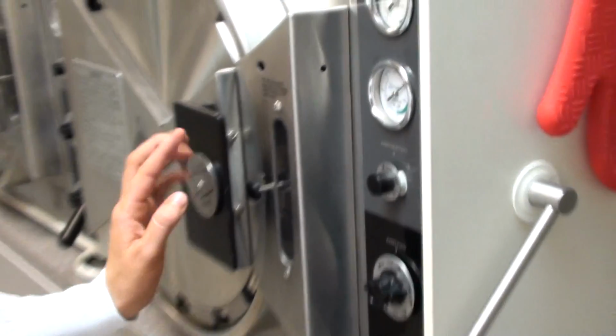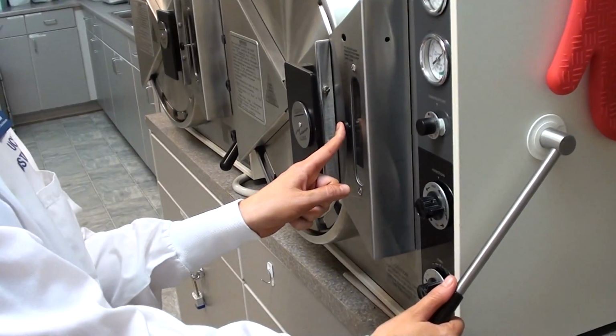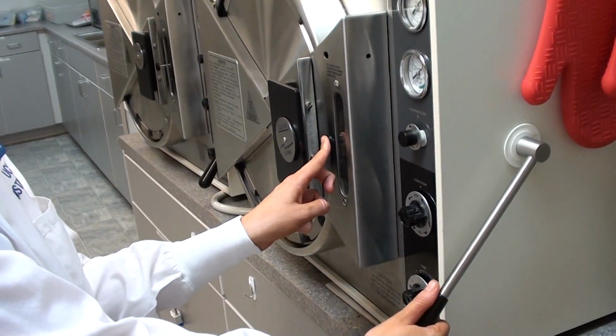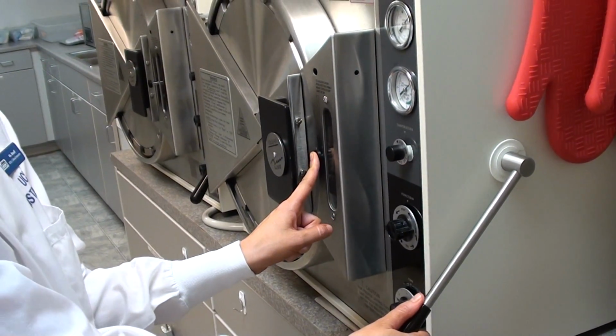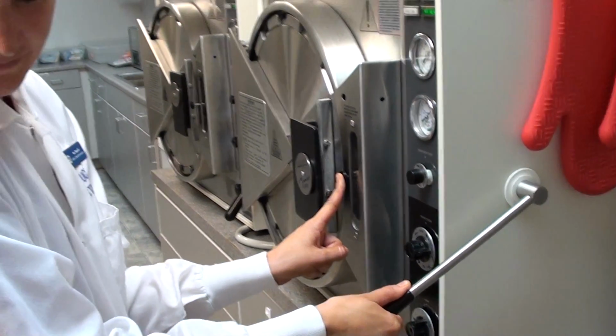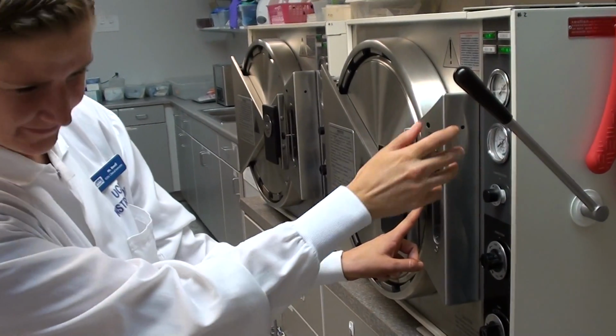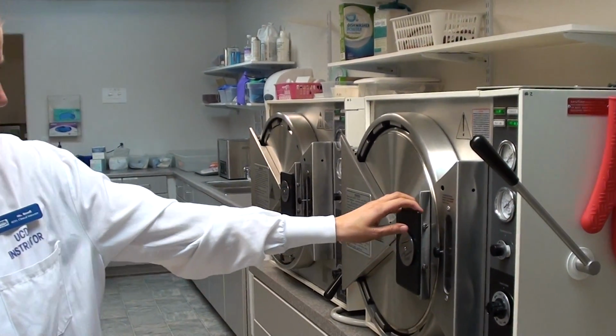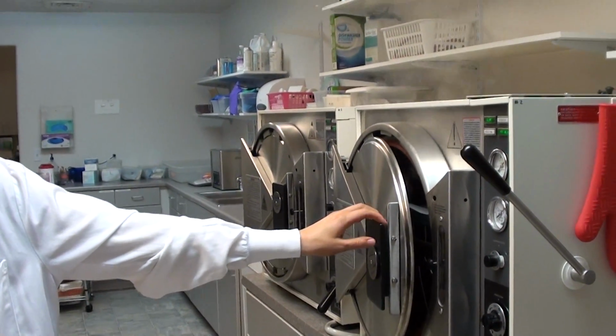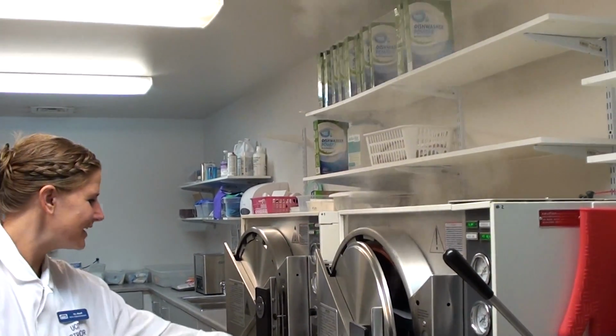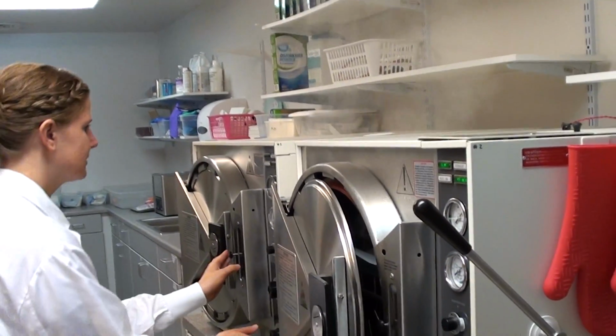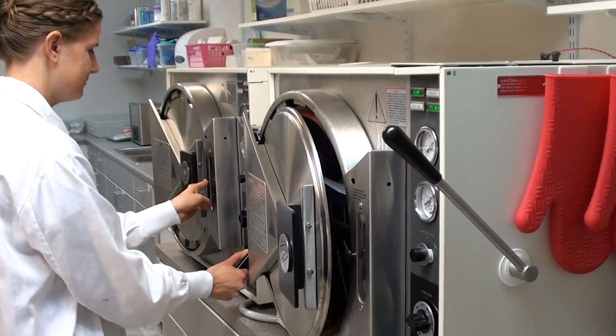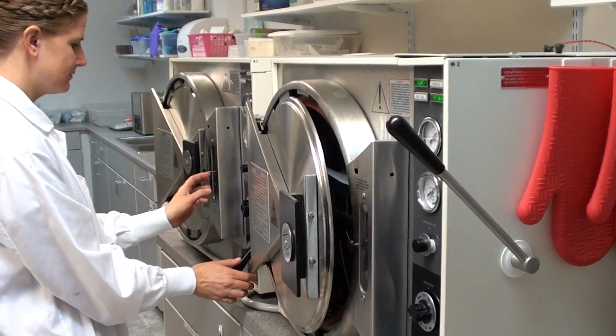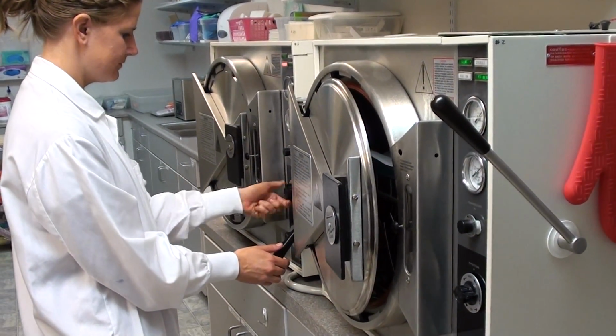She's going to open the door by depressing the open door button with her left hand and lift the door handle with her right hand. Please avoid the steam that is released at the top of the unit when you open the door. Notice how she turned her head away and she's stepping away. Ooh, very hot. Lava. Now she's going to leave the door slightly open and the instruments in the autoclave for about 15 minutes to allow the instruments to dry.